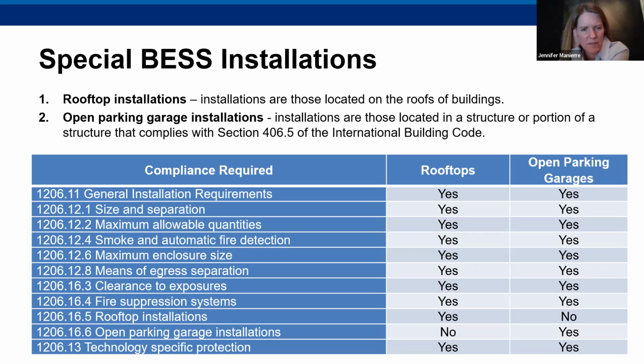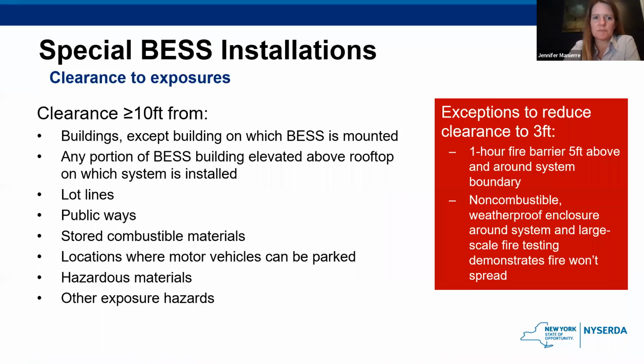And a lot of these compliance items are the same things that we've been talking about before: those size and separation requirements, the maximum allowable quantities requirements, and so on. And then these extra little sections where there's something special for rooftops and open parking garages. Like many of the other installation types, they need that 10-foot clearance again. I won't go through every part of it, but the one that sticks out a little bit here is that second bullet: any portion of the energy storage system building that is elevated above the rooftop on which the system is installed. You need a 10-foot clearance from that as well. And so that's a little bit unique to these ones versus the other areas that we've talked about them being installed before.